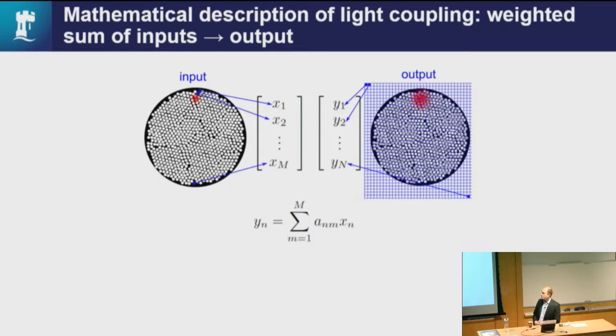Yeah, so in these imaging fiber bundles here, they've designed them for white light imaging. So particularly if you're using green wavelengths, which if you look at a lot of the research on these, they tend to use, then the fibers are far enough apart and have a big enough refractive index difference to avoid too much light leaking out. However, to maximize resolution, they still have crammed them in. So if you have a 2 meter length, you'll find that you start to be able to visually notice the leaking. Because you can't perfectly isolate them, there might be a small amount of coupling per unit length. But if you have it long enough, that happens.